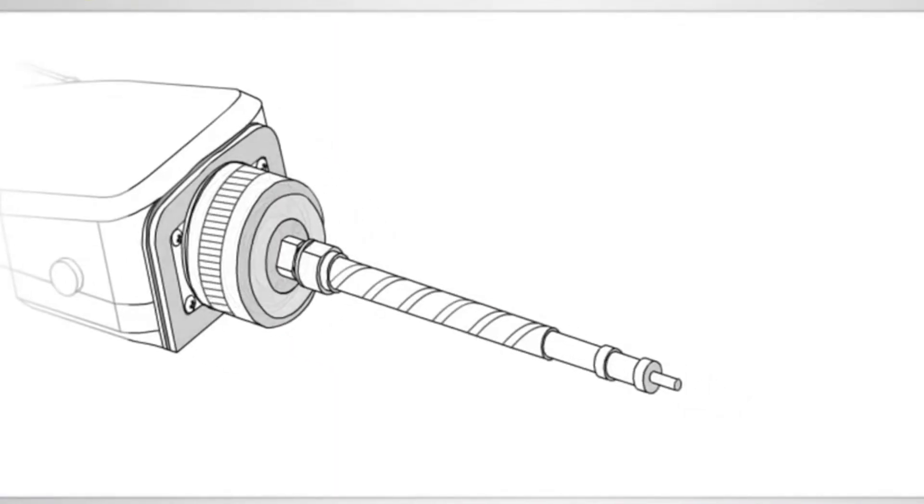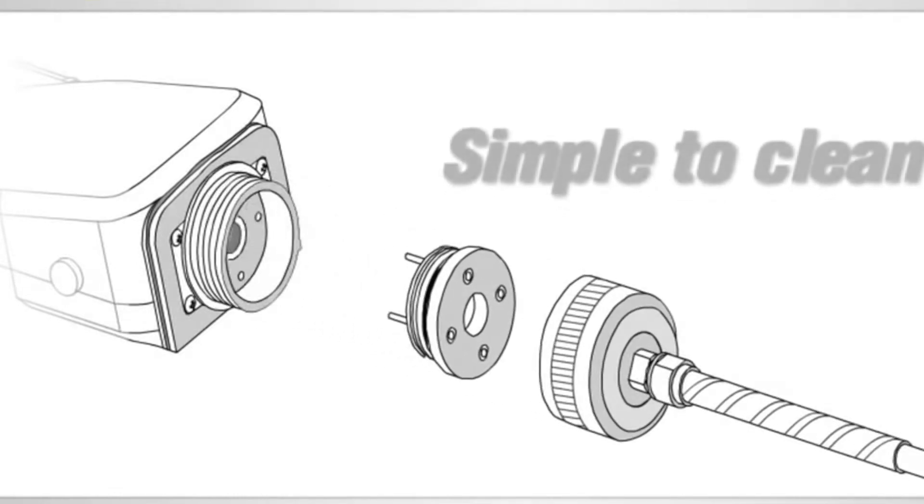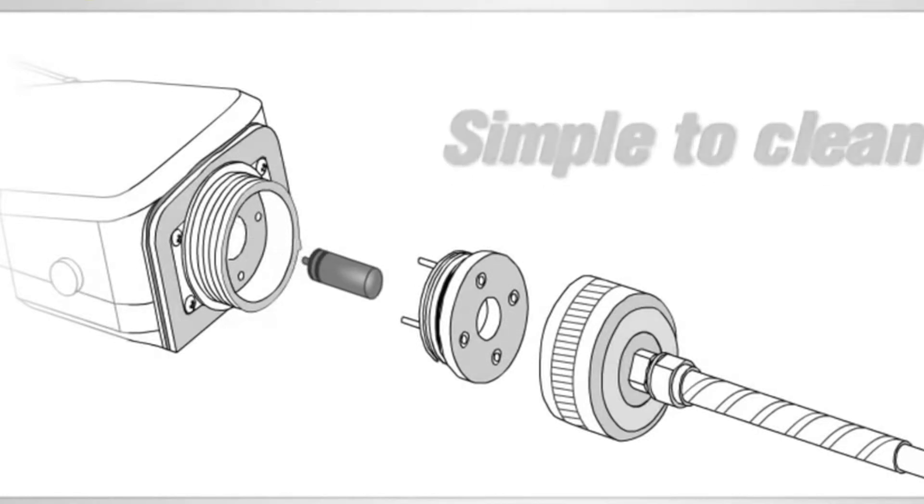The MiniRAE 3000 features patented duty cycling technology for cleaning the PID lamp and sensor. Both come apart in seconds for easy maintenance without any tools.